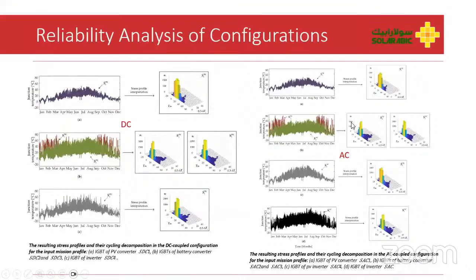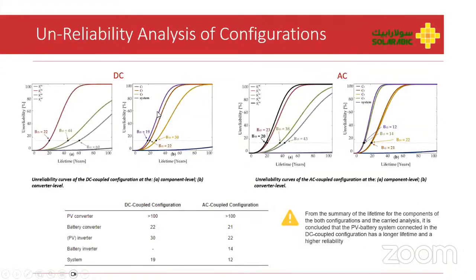This is just a vectorial differentiation of the stress profiles between the DC coupled electronic devices within the power converters and the AC coupled power electronic devices in an AC coupled system. So we see certain uncertainties in terms of the stress profiles. These uncertainties are lumped together, and based upon that, we develop the unreliability analysis and the curves for the DC coupled configuration and the AC coupled configuration. After studying the complete scenarios, we find that in a DC coupled configuration and an AC coupled configuration, the life of the PV converter is almost the same.